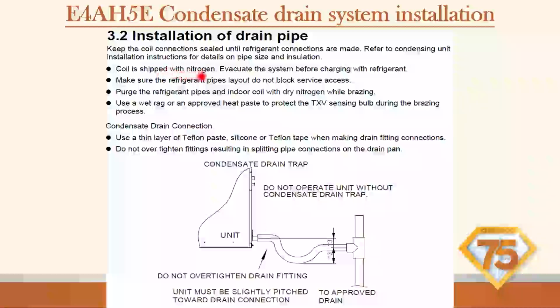Coil is shipped with nitrogen. Again, it's nitrogen under a minimal amount of pressure, guys. I know when I used to pull those caps off the evap, I'd want to hear that hiss. Sometimes you're not going to hear that hiss because it's just bare minimum pressures in there. And you think that there's a leak, but they just barely pressurize those things for transport. So you're going to release the nitrogen, you're going to braze up, you're going to evacuate the system before charging with the refrigerant.